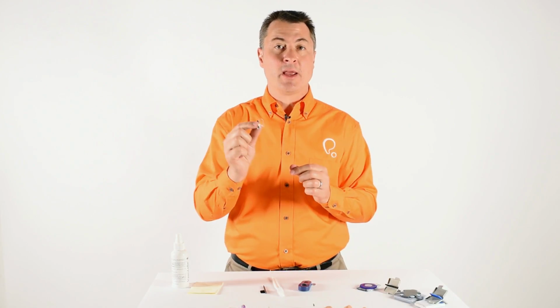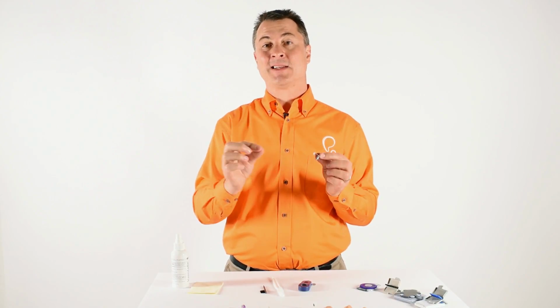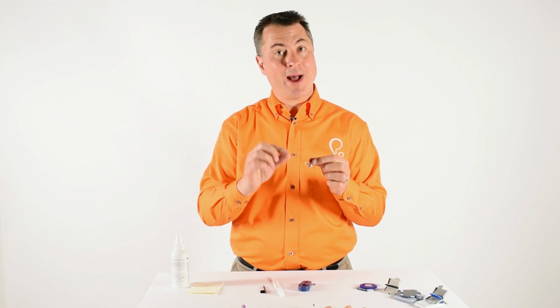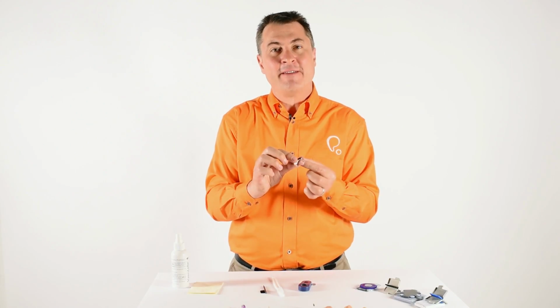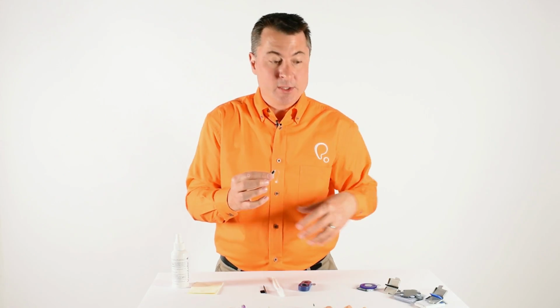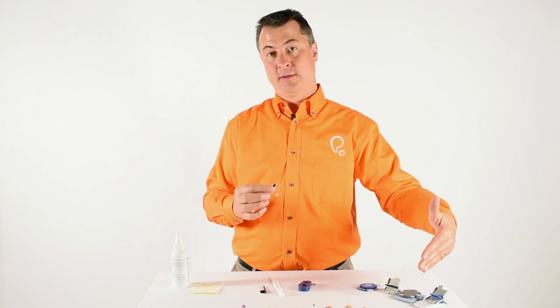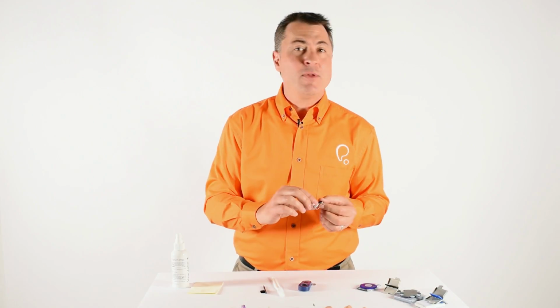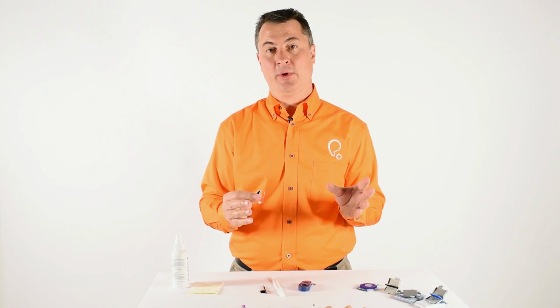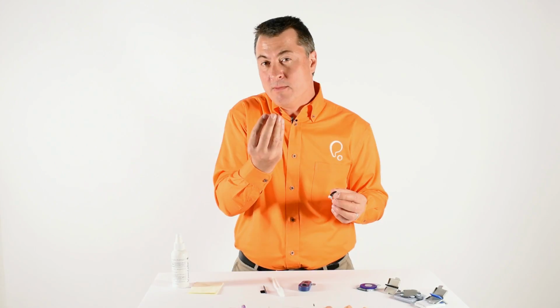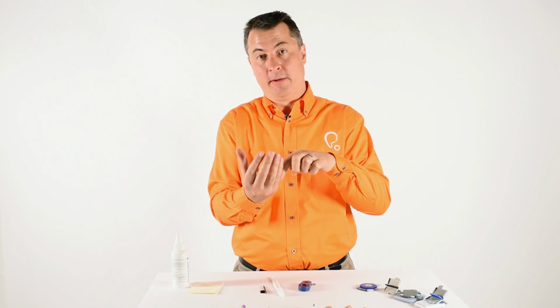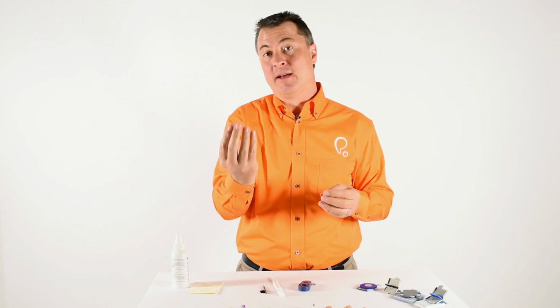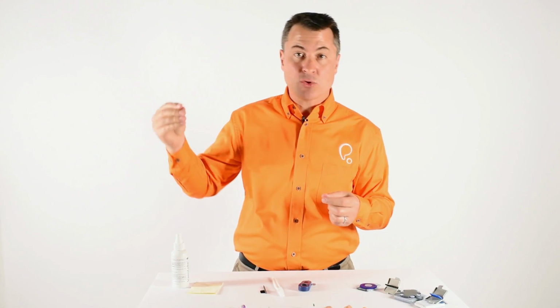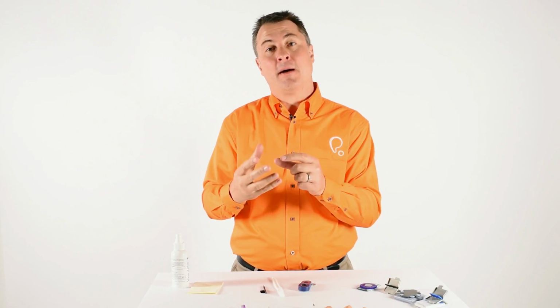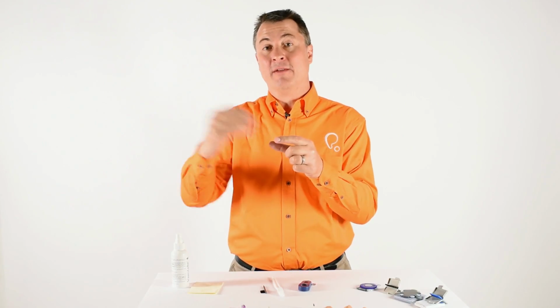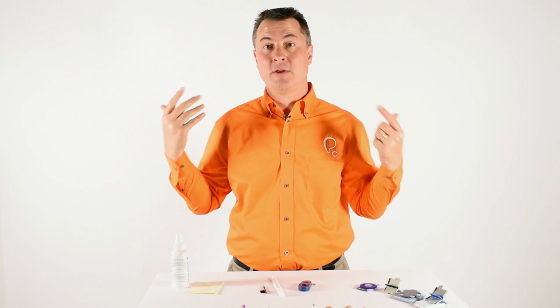The next step is, most of the hearing aid companies are getting smart. They're putting what's called a wax guard on the hearing aid because they know wax often clogs the end, and cleaning can be fairly fine. It's a tiny process. Here are a few examples of different wax guards found in hearing aids. Even though there are different kinds, the concept is very similar. They've designed a very miniature plastic cup with holes in the bottom, and that plastic cup fits inside the speaker. As the wax tries to get in and damage the speaker, the little plastic cup stops it. But the problem is the wax can fill that little cup, blocking it, and then all of a sudden your hearing aid doesn't work.